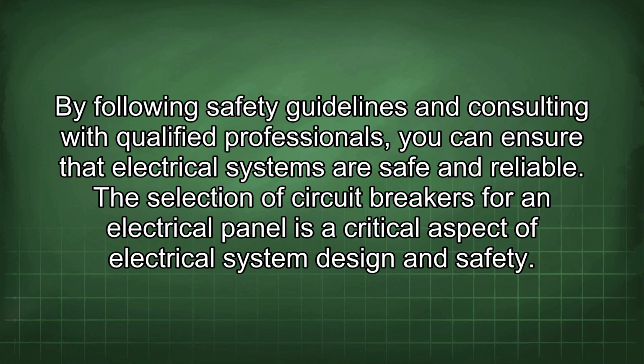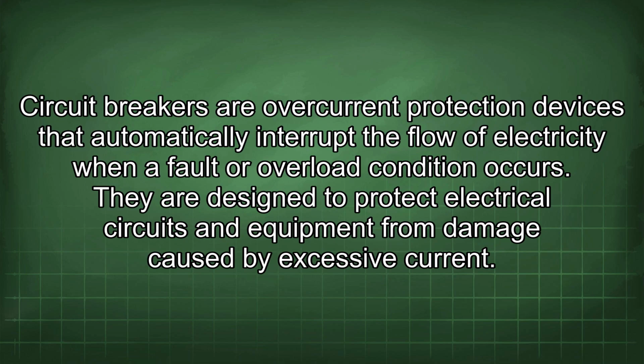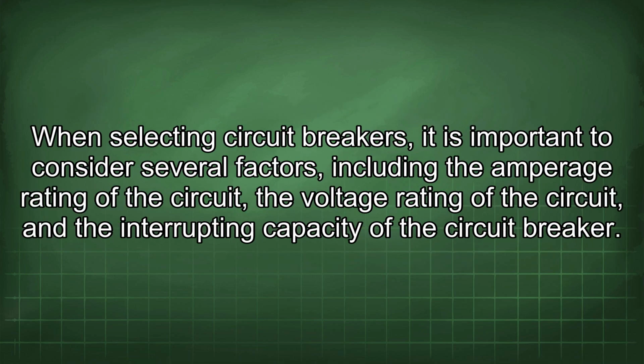The selection of circuit breakers for an electrical panel is a critical aspect of electrical system design and safety. Circuit breakers are overcurrent protection devices that automatically interrupt the flow of electricity when a fault or overload condition occurs. They are designed to protect electrical circuits and equipment from damage caused by excessive current. When selecting circuit breakers, it is important to consider several factors, including the amperage rating of the circuit, the voltage rating of the circuit, and the interrupting capacity of the circuit breaker.